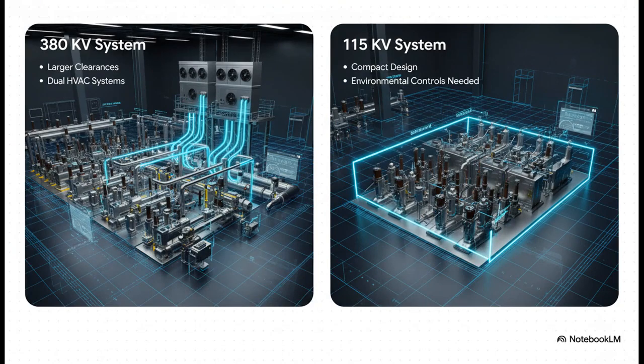Not all of these GIS halls are created equal. The design changes big time depending on the voltage. A 380 kilovolt room, that's the heavyweight champion. The components are massive, you need more space, you even need powerful cooling systems to handle the heat. Compare that to a 115 kV room, which is more like a middleweight, still incredibly powerful, but much leaner and more compact.